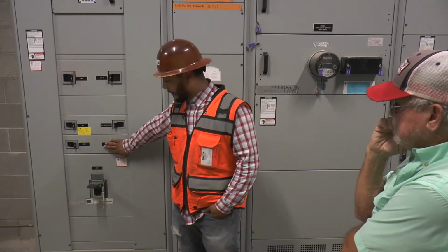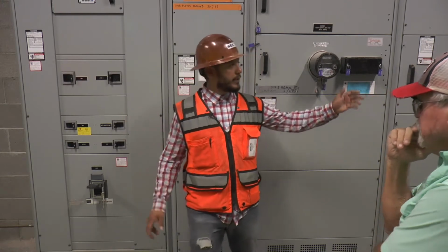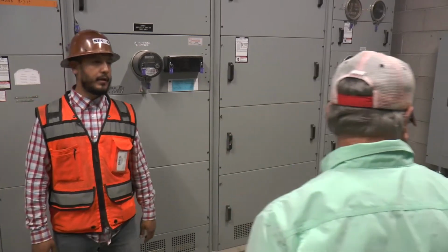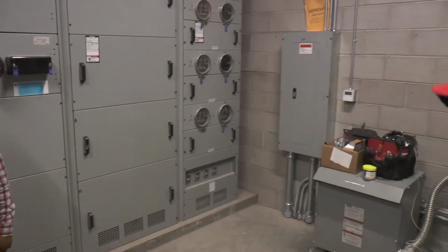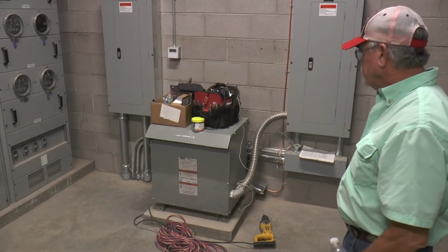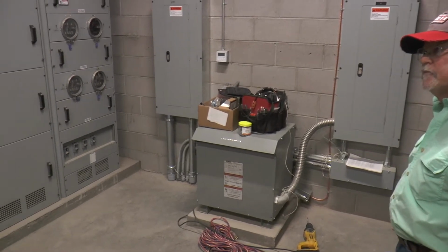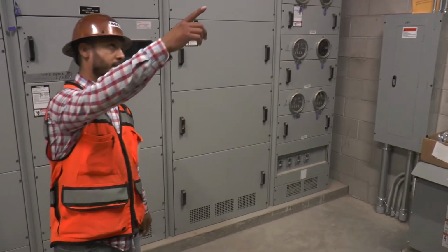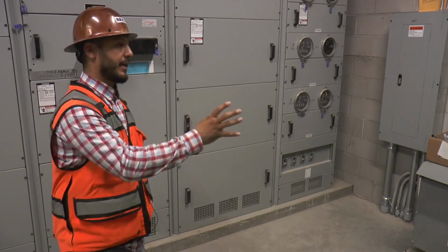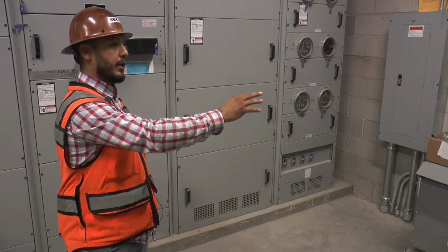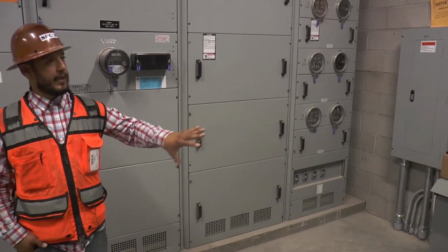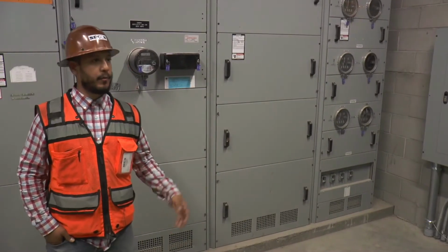And 1H1 is pertaining to all your back of house, which is right here. This panel steps down to a 75 kVA to a 120/208 to give you power here in these equipment rooms, all your service outlets, any convenience outlets here on the first floor. It also pertains to the lobby area. Air handlers will be coming out of here. This actual air handler gets piped out of here as well. All your equipment areas on this back of house, the air handlers come out of this panel. And that's pretty much what these panels handle: back of house equipment, lighting, and convenience outlets for maintenance purposes back here.